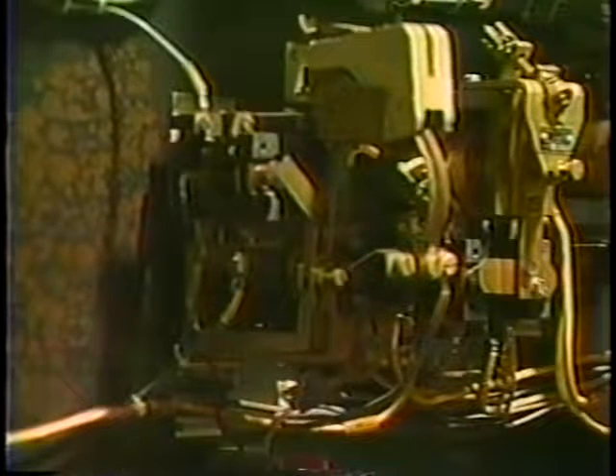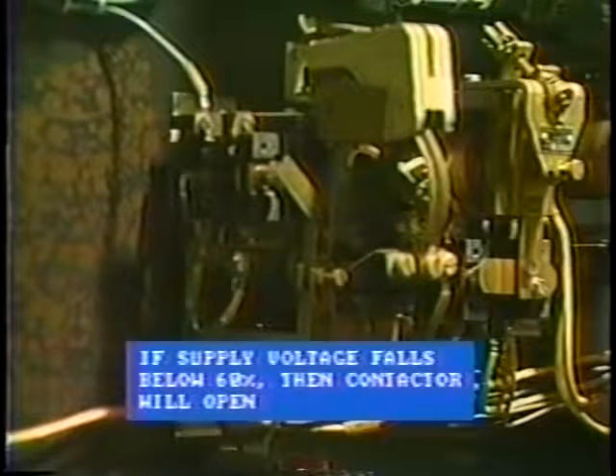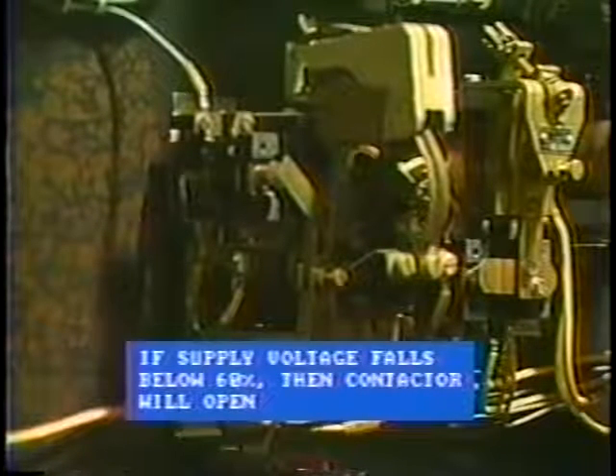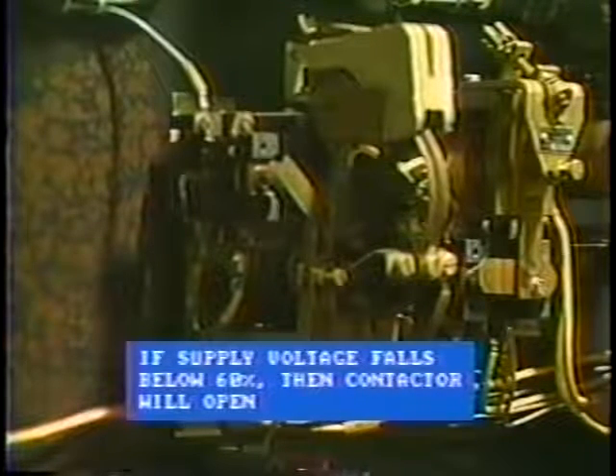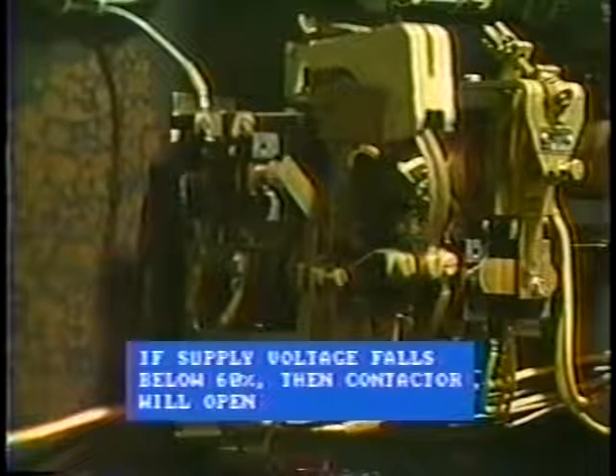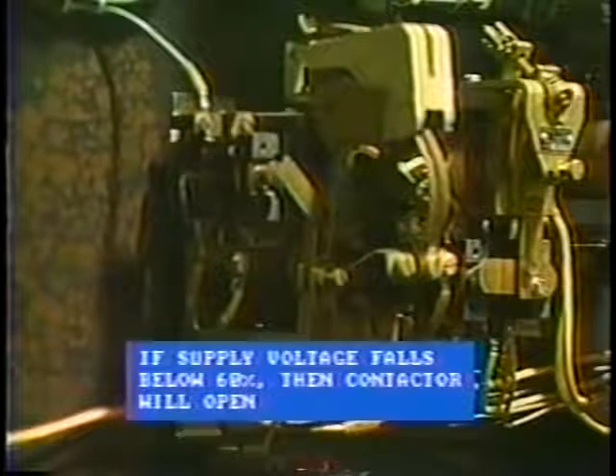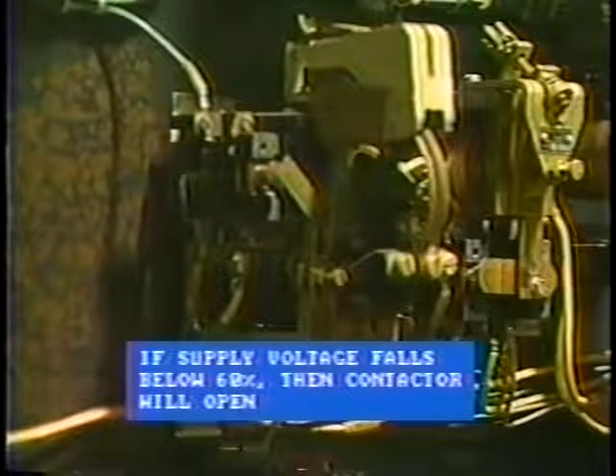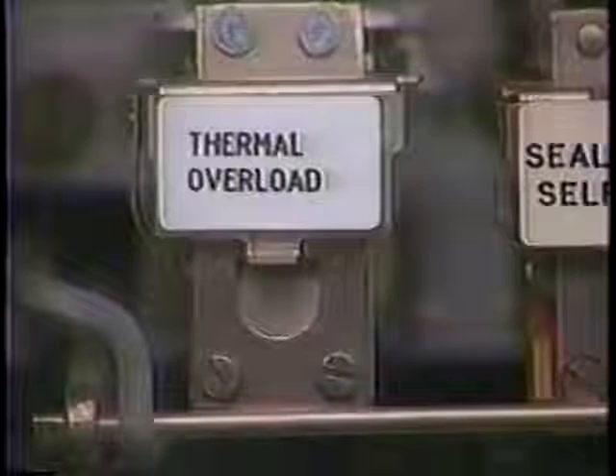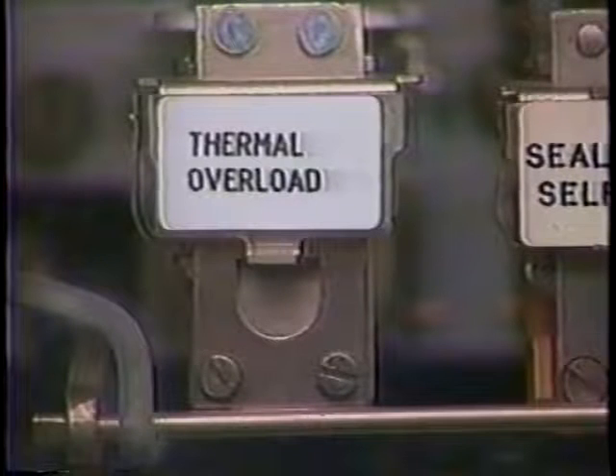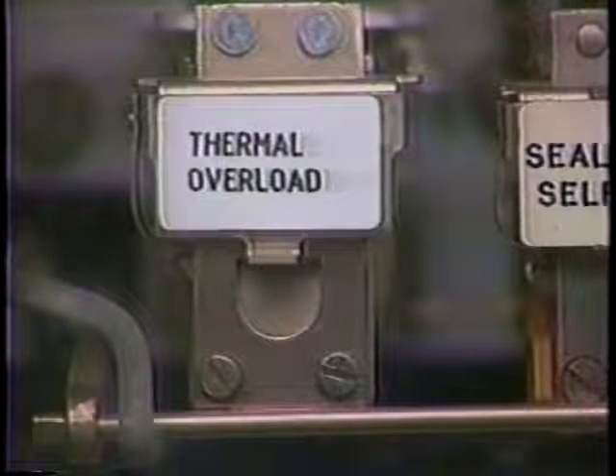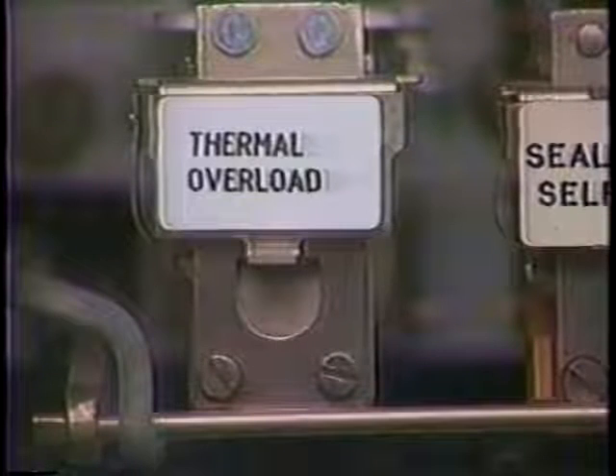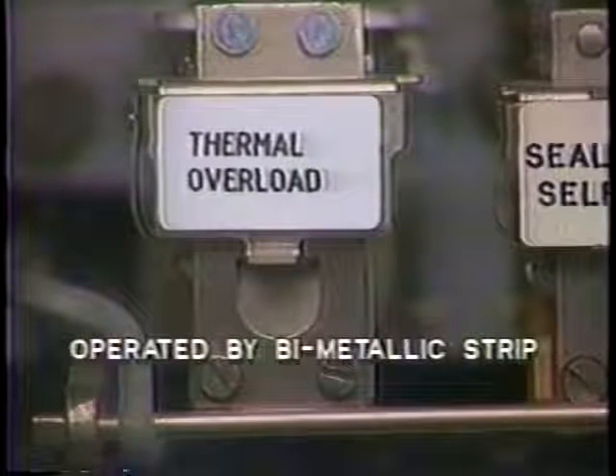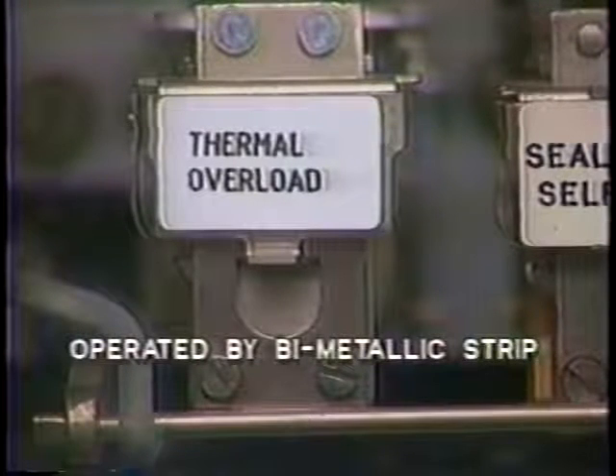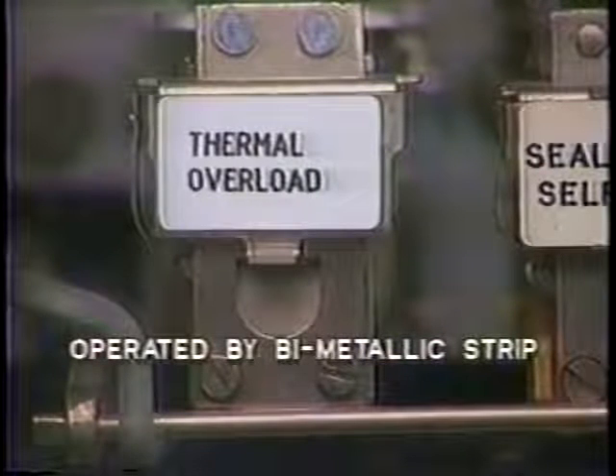The contactor is held closed by the contactor coil. If the supply voltage falls below, say, 60%, then the contactor will open and remain open until the operator effects a manual start. So this provides some protection for loss of voltage. Also, a thermal overcurrent relay is usually built in to protect the motor against overcurrents. Heavy overcurrent heats a bimetallic strip which opens and interrupts the power supply to the contactor coil.